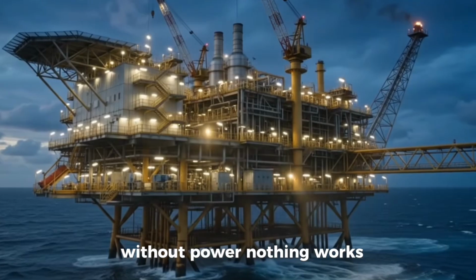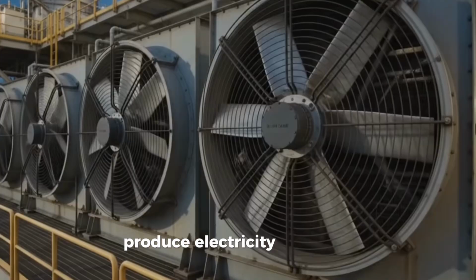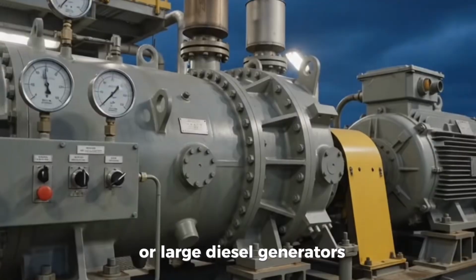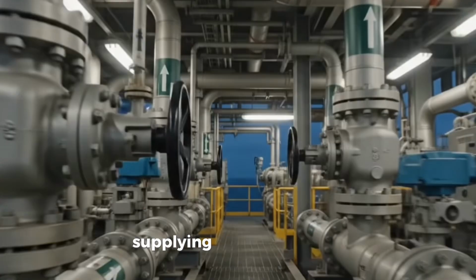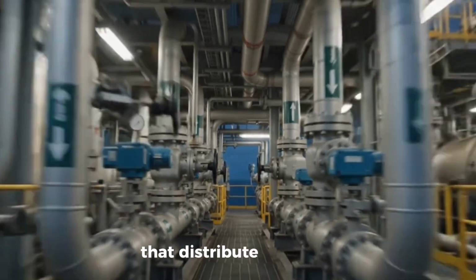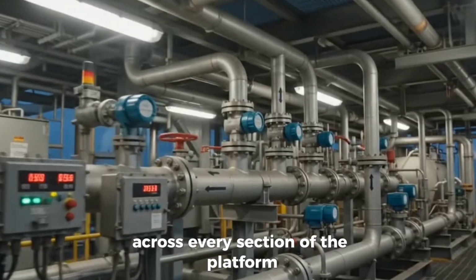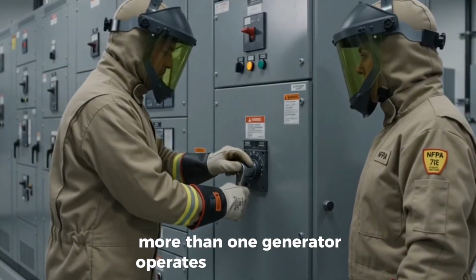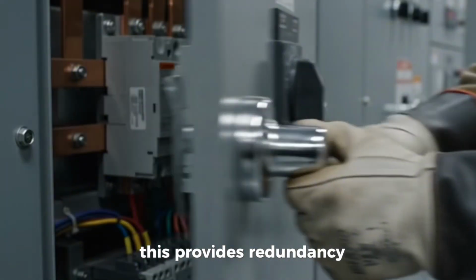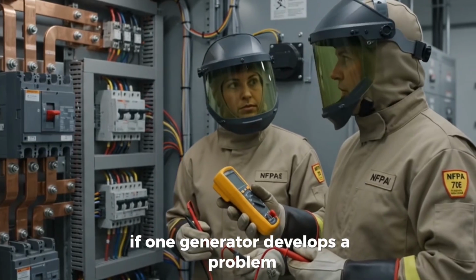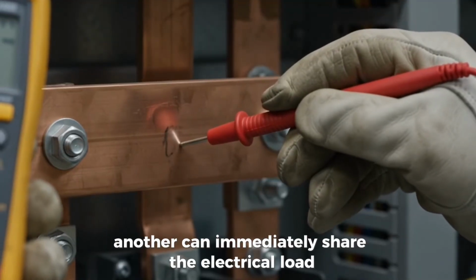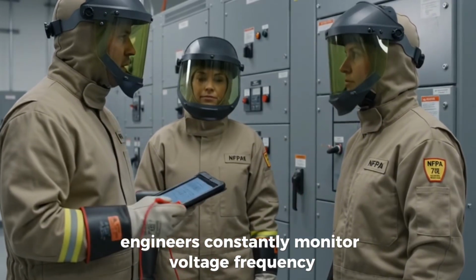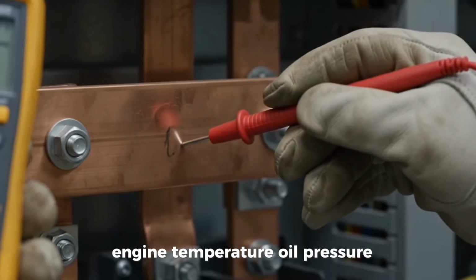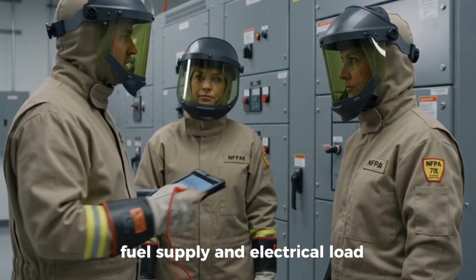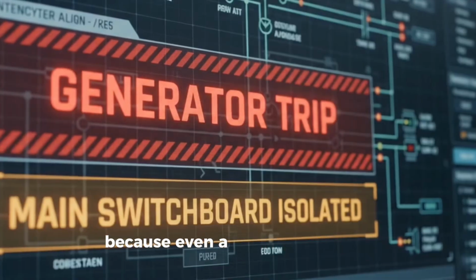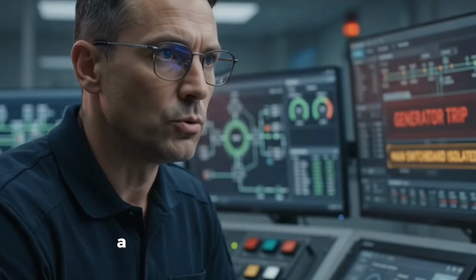Without power, nothing works. Most offshore installations produce electricity using gas turbines or large diesel generators. These generators operate around the clock, supplying electrical power through massive switchboards that distribute electricity across every section of the platform. Normally, more than one generator operates at the same time. This provides redundancy. If one generator develops a problem, another can immediately share the electrical load. Engineers constantly monitor voltage, frequency, engine temperature, oil pressure, fuel supply, and electrical load. Every reading is carefully watched because even a small abnormality can quickly become a much larger problem.